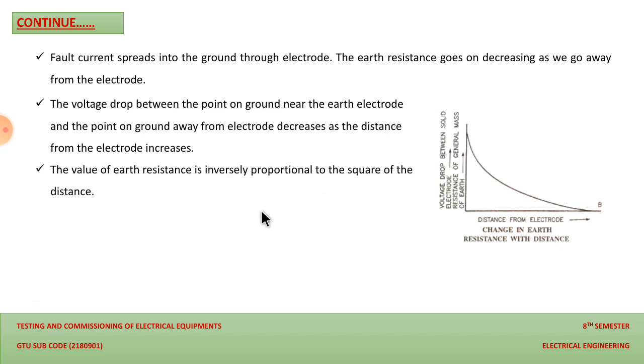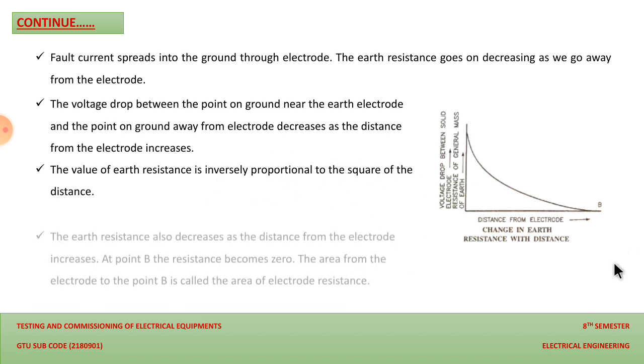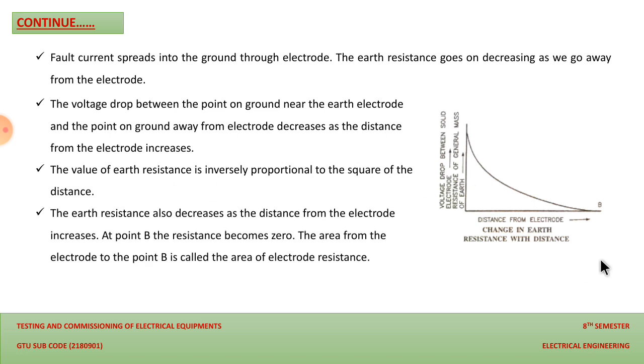So the value of earth resistance is inversely proportional to the square of the distance. If the distance is more, the earth resistance will be less. If earth resistance is less, it means the distance is more, and if earth resistance is more, the distance is less. So both are inversely proportional, and we have to keep that in mind while providing the earthing. The earth resistance also decreases as the distance from the electrode increases. At point B you can see that the resistance becomes 0, and from this point to this point is called the area of electrode resistance. This is the place where we should keep low resistance while providing an earthing rod, earthing pit or earthing electrode.